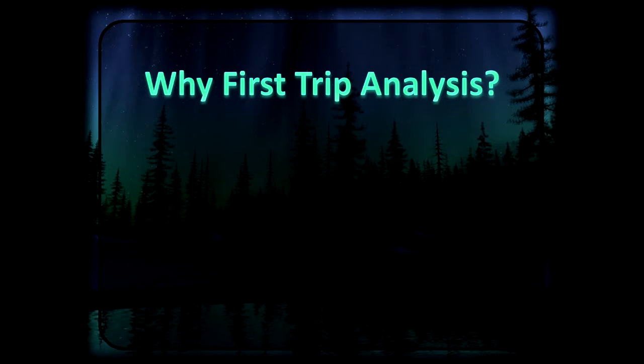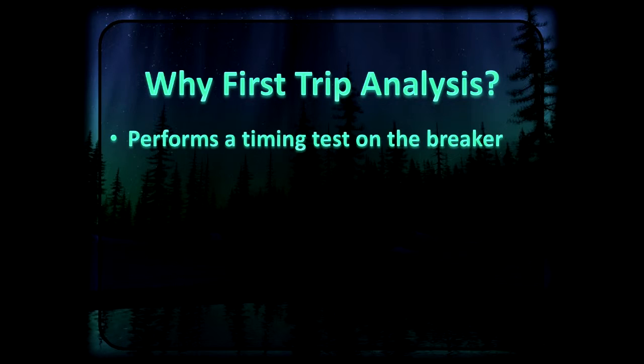So the first question we have is, why do a first trip analysis? Well, what a first trip analysis accomplishes is it performs a timing test on a breaker. For those who may not be familiar, breakers are large equipment that interrupts power that's flowing to the substation. They're anywhere from 7,000 volts all the way up to 230,000 volts. Whenever a fault hits the line, a breaker has to open and isolate the fault and cut the power off. So this is a test that will measure the timing of that breaker to make sure that it's opening fast enough to perform its duties without damaging other sensitive equipment in the substation.